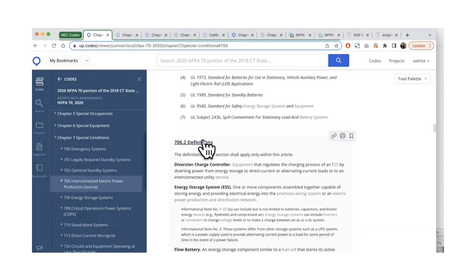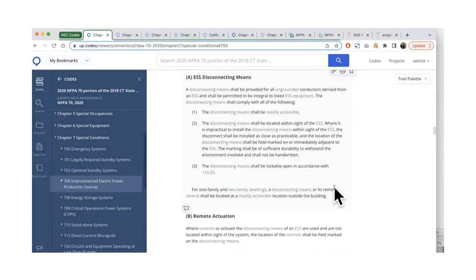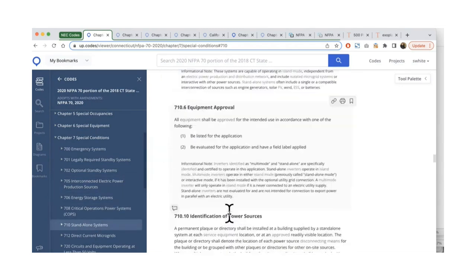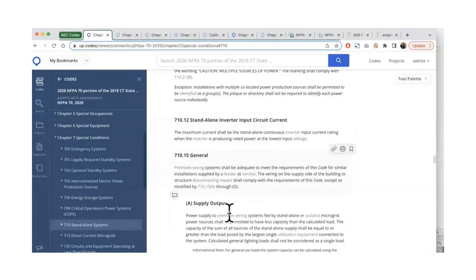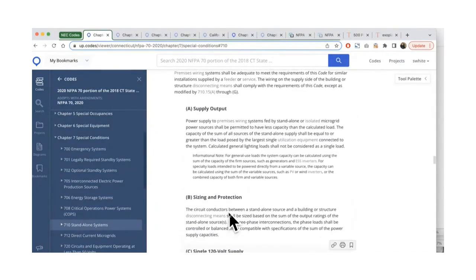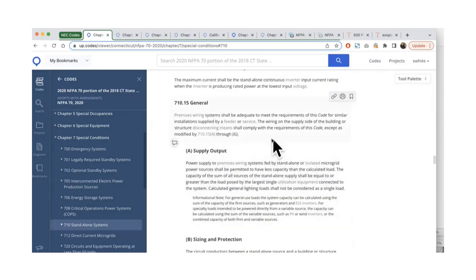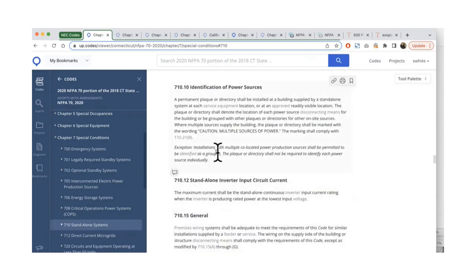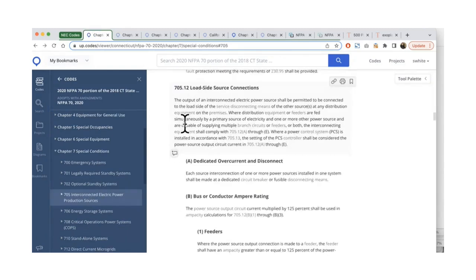Yeah, so what you need there, let's see, 1 and 2 family dwellings, a disconnecting means or its remote control shall be located readily accessible outside of the building. So in that case, you were talking about a multi-mode inverter. So you need to be able to have a disconnect for that standalone portion of the system outside of the building. And you can also find that in 710 too, or if you went over here, it talks about identification of power sources, but you would treat it like a standalone system too. You have to comply with 706 and 710. Maybe the best place to look at it was where we just were over here. And so that's pretty much what you have.